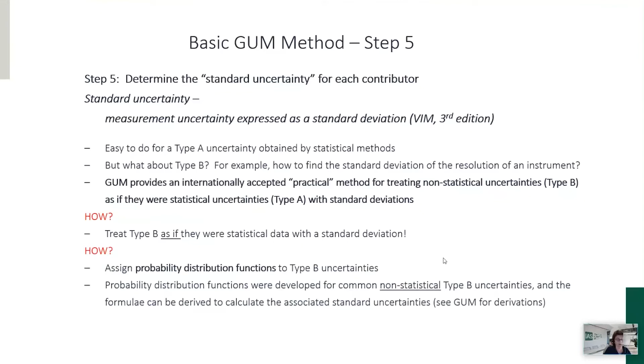But if you need to know more about which probability distribution function to use, we don't have time to get into that right now. But if you go to the end and look at the bibliography I gave you, you can do some further reading. So let's look at what we have right here and what we've assigned. The repeatability we know is assumed to be a Gaussian or normal distribution, and we already arrived at that 60 microvolt by taking the standard deviation. So we don't have to do anything else to this one. The standard uncertainty is equal to the standard deviation of the type A, and in this particular case, we're using the standard deviation of the mean.